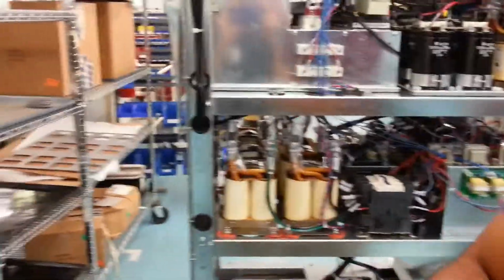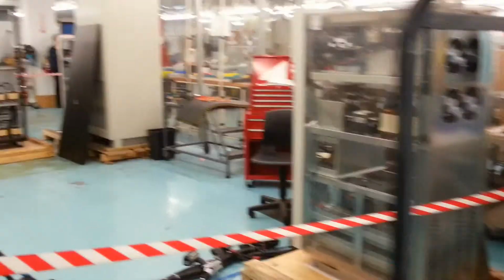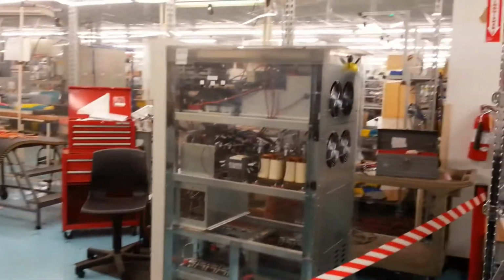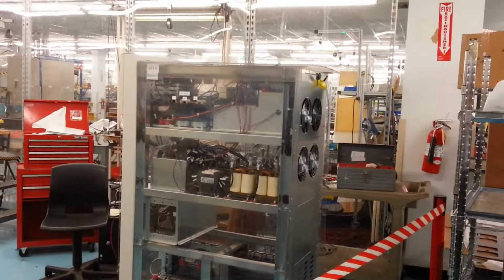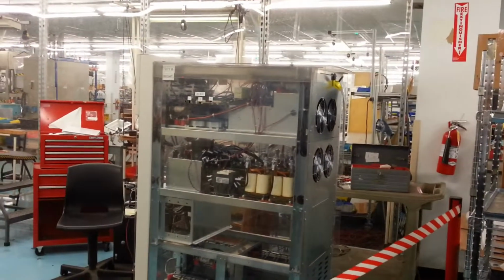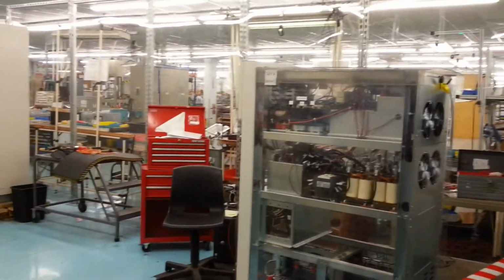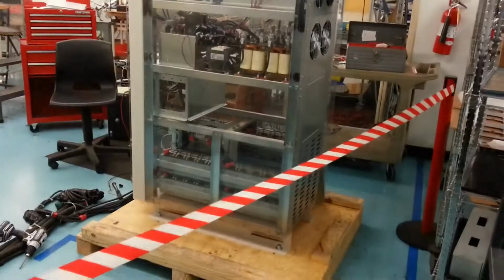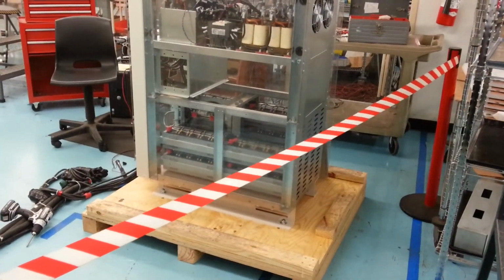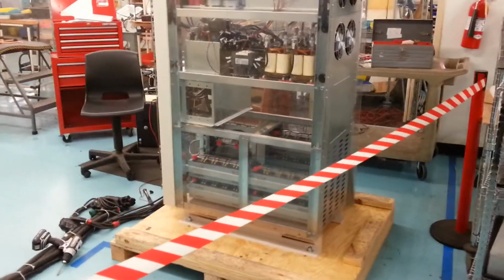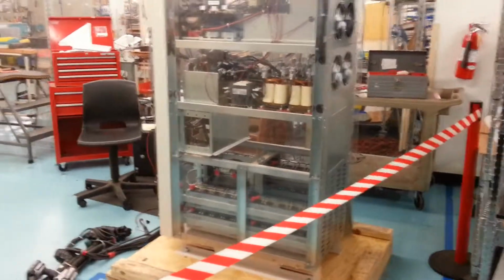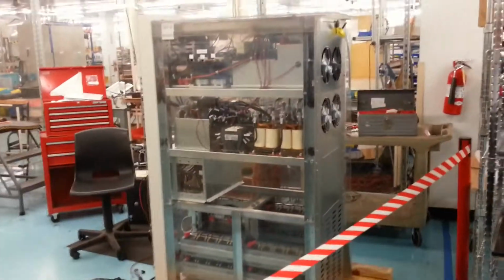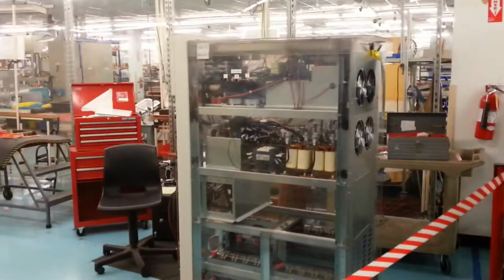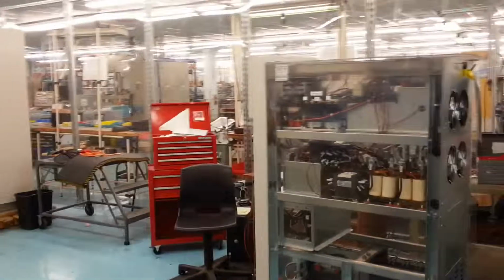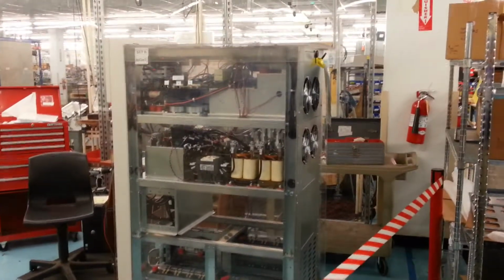Okay? And then here we have the test facility. Like I mentioned before, all of our units go out 100% load tested, every one of them, no exceptions. So most times they'll get run overnight, like full load. You see how this one here on the bottom seems to be a battery unit. In that case, all those are in series on one side, series on the other, 2 strings in parallel. There's fuses in there protecting each actual section. Each has its own fuse.